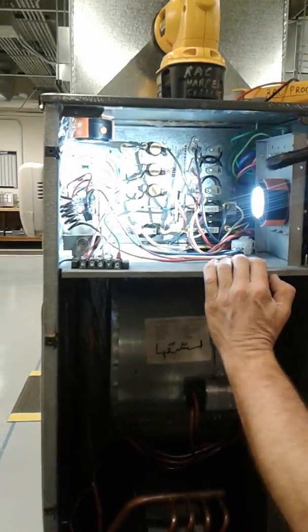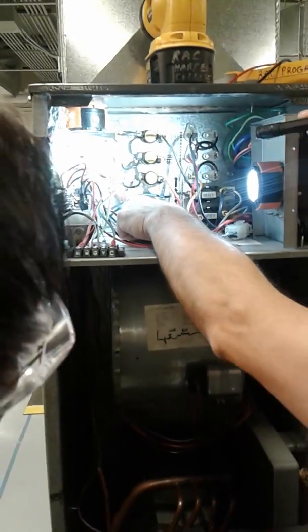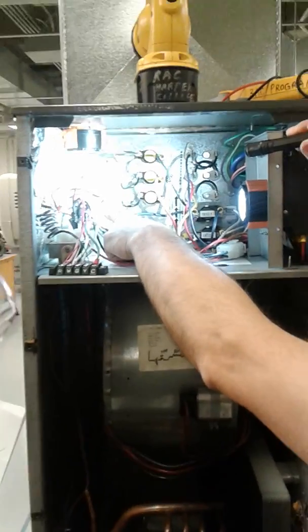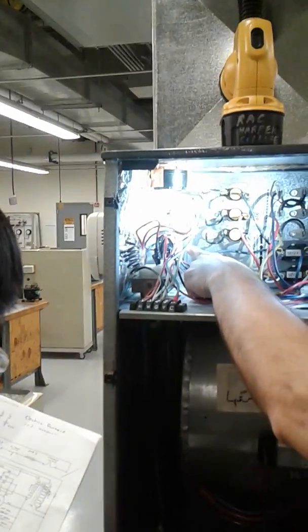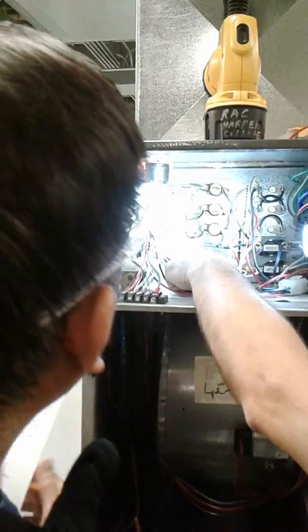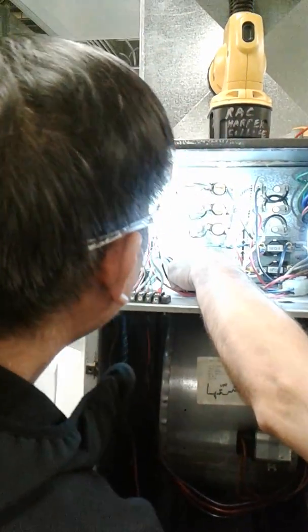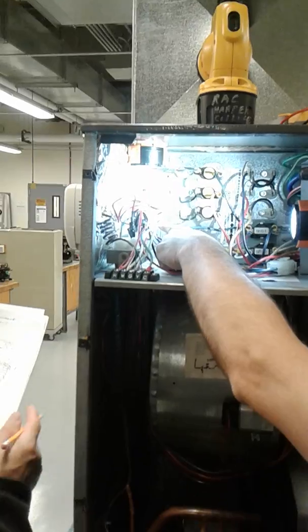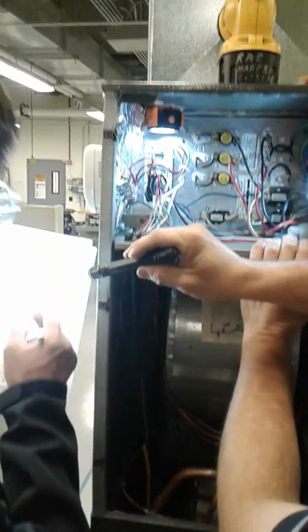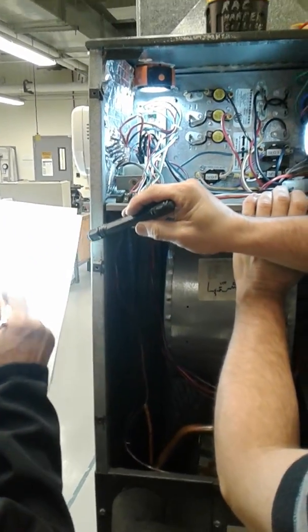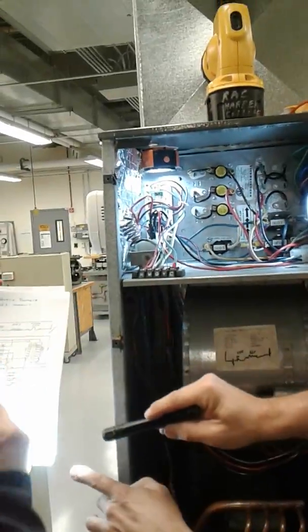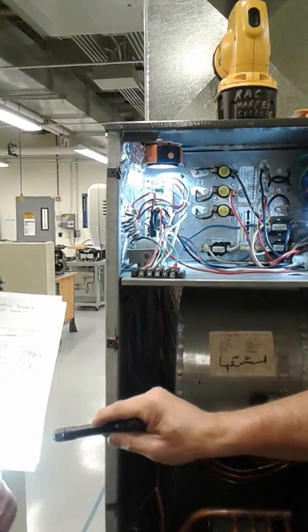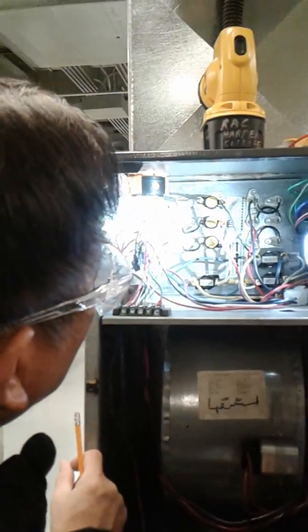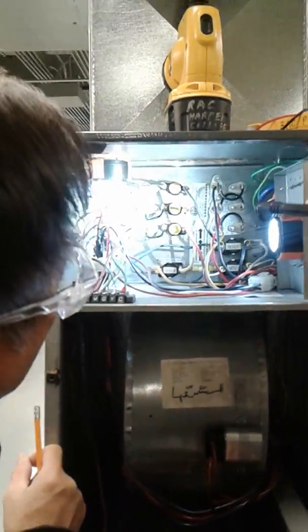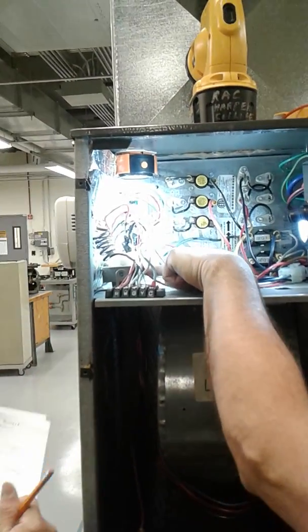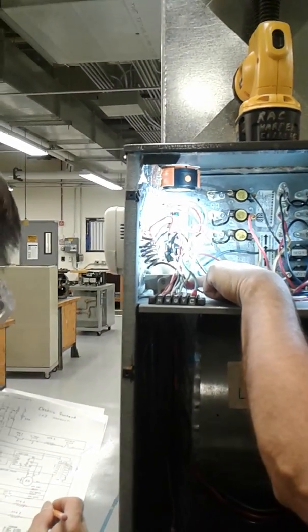Okay? Now, this back here, guys, what's that circuit board back there? What is it? What's the name of that circuit board back there? EBTDR, electronic blower time delay relay. Okay? It's right there on the schematic. Okay, EBTDR. If you don't remember what EBTDR stands for, remember, it's in your notes, and it's also in the notes on the bottom of that schematic. Okay? Now, another thing we've got here is the transformer. 240 volts steps it down to 24 volts.